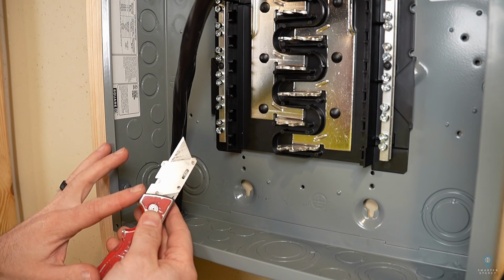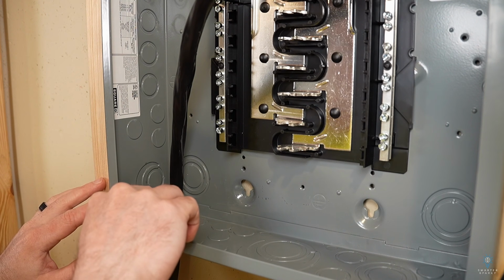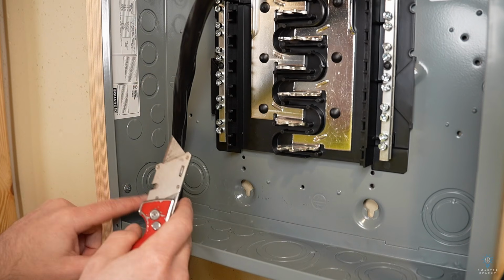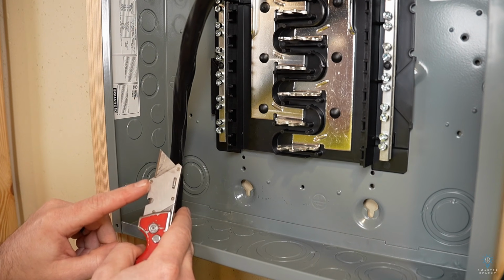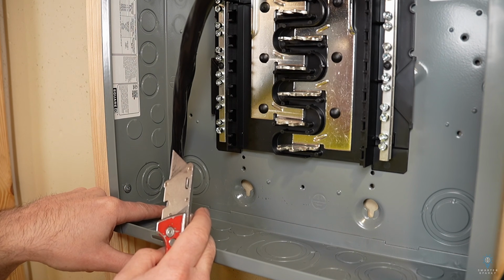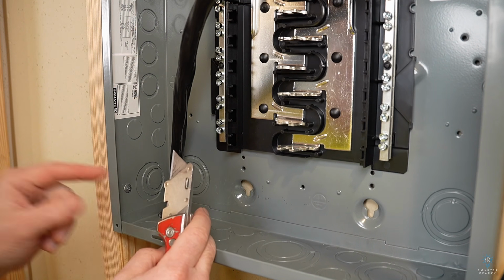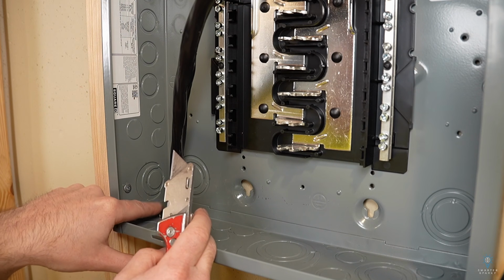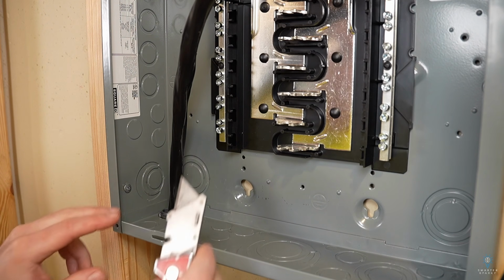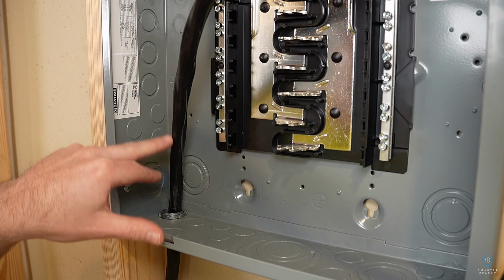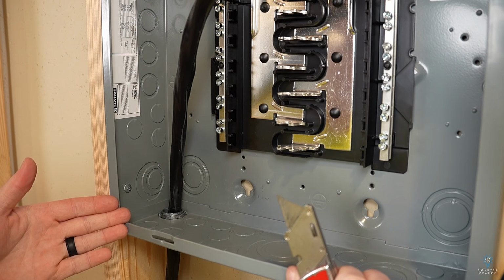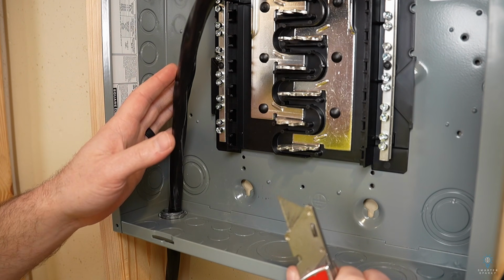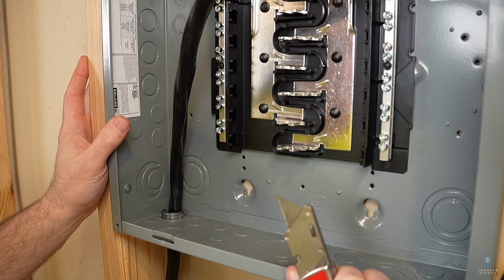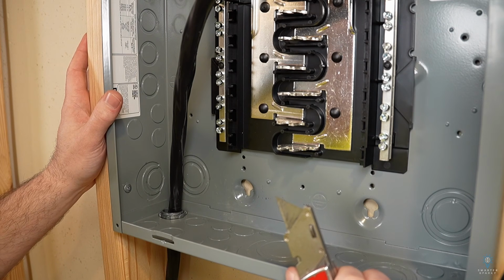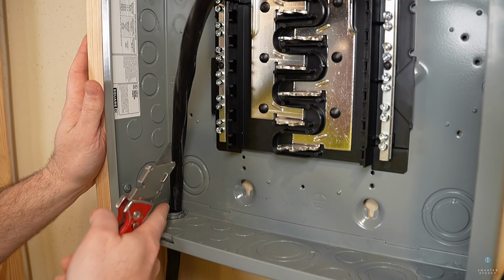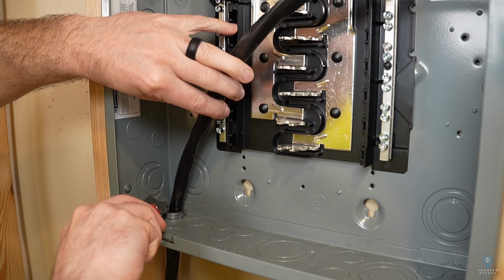I'm gonna use a razor blade knife to score the jacket on the sheath. If you do use the razor blade method, make sure you only score very lightly the outside insulation. We do not want to cut through into the inside conductors. They do make special cable sheath strippers, but if you're installing a 100 amp sub panel, you're gonna be using larger cable, and I don't know if I've necessarily ever seen a special stripper for those. So in this case, I'm just gonna score the outside sheath with a razor blade, and we're gonna pull that jacket off.